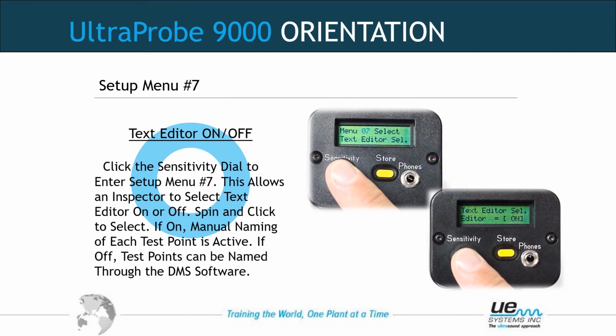Back to the main setup menu, we rotate the sensitivity dial to number 7, which is text editor on or off. This allows us to turn the text editor on or turn it off. Having it on allows us to name or rename a test item while we're in the field in a route. By turning it off, it turns the text editor selection off during the storage process, which makes the storage process faster. Typically, we should never rename anything on the unit while we are in the field. This could get confusing and mess up the entire route. It is better to jot down on a piece of paper or a note what needs to be renamed or reorganized and wait until we get back to the computer and to the software, and then we can make our changes then.